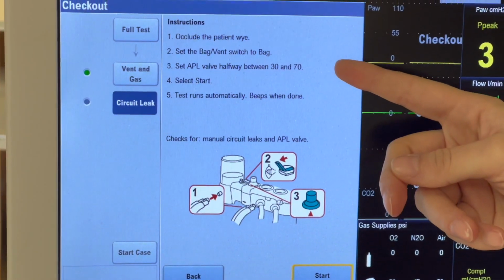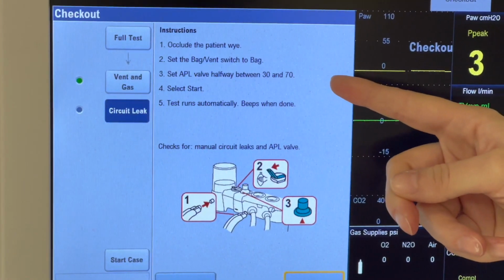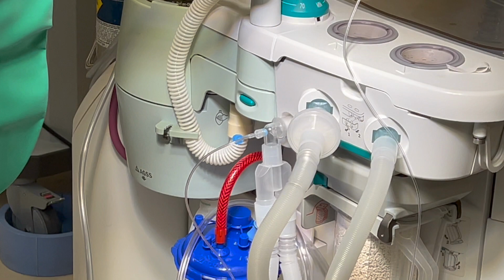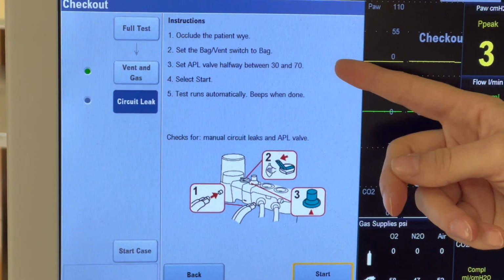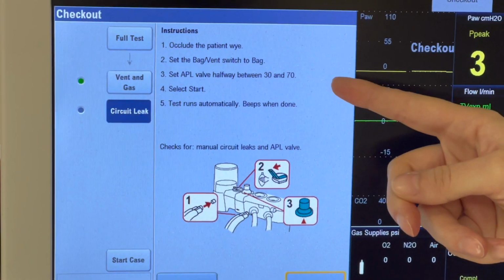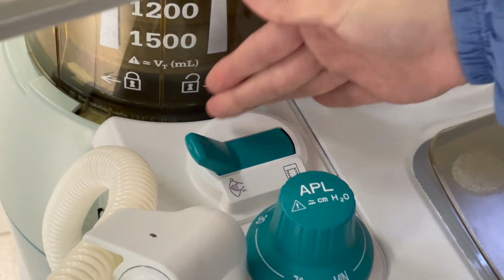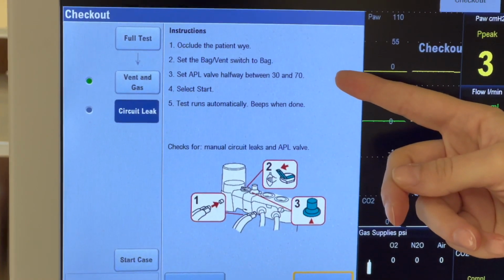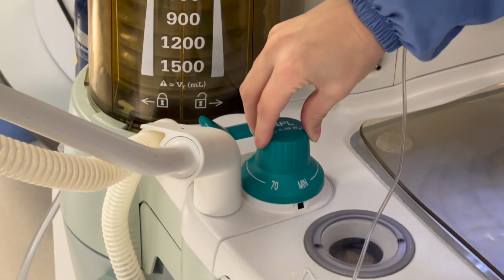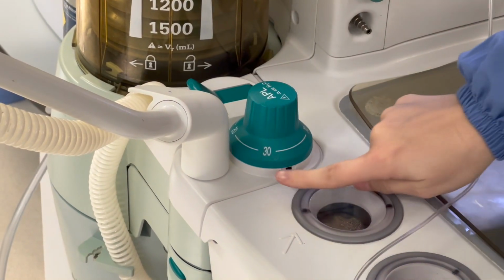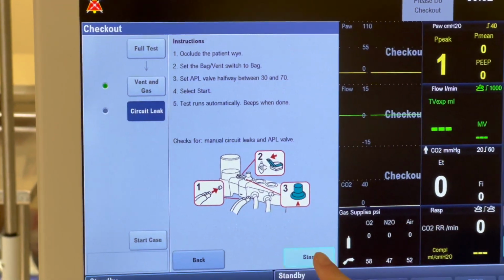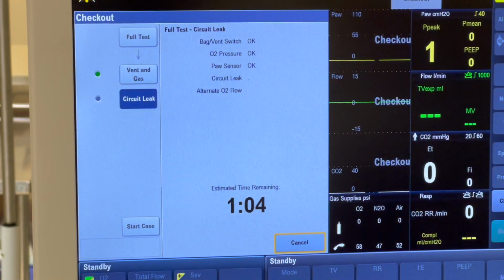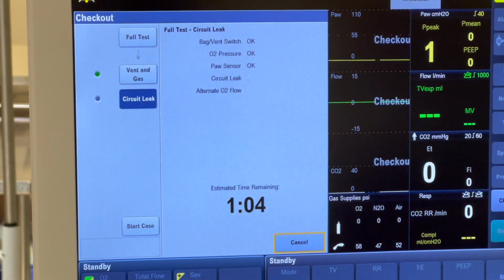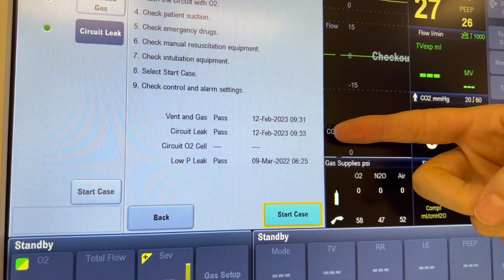Perfect, so now follow these instructions one by one. First, we're going to make sure the patient Y is still occluded, which it should be from the last test. Then we're going to go ahead and set the bag vent switch to bag. Then set the APL valve between 30 and 70. Halfway is fine, or just after 30 is also acceptable. And then we're going to hit start. This takes approximately 1 minute to complete. We're going to fast forward for time purposes. Once that's done, you should get a vent and gas pass with a date and time and a circuit leak pass with a date and time.